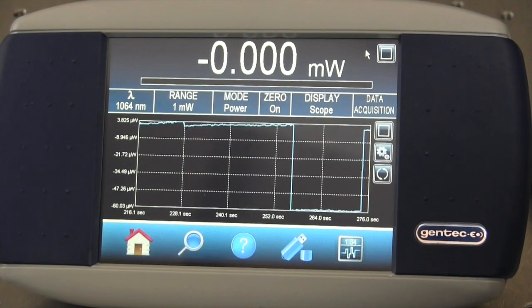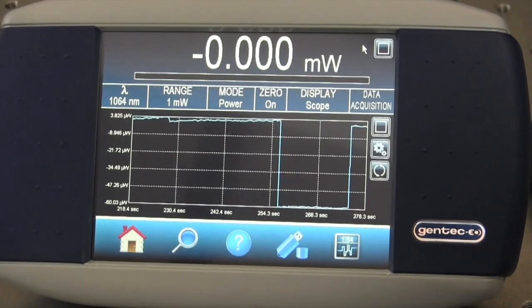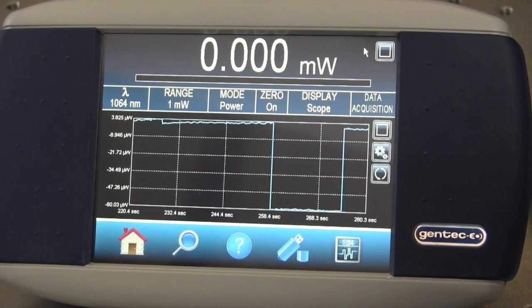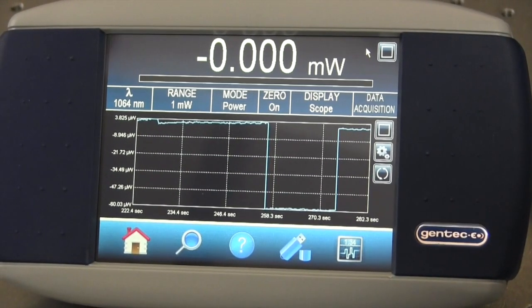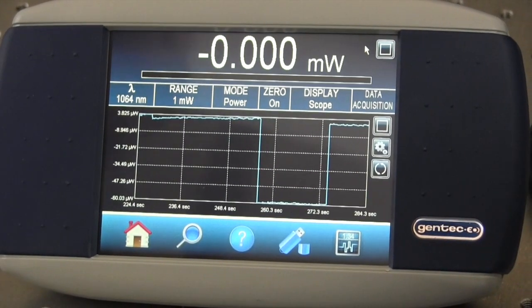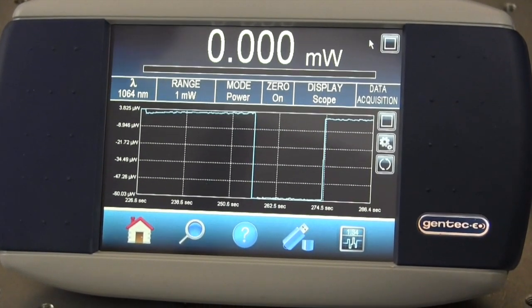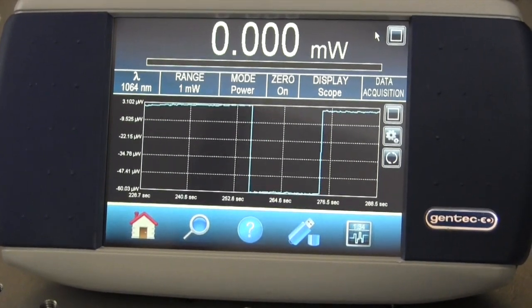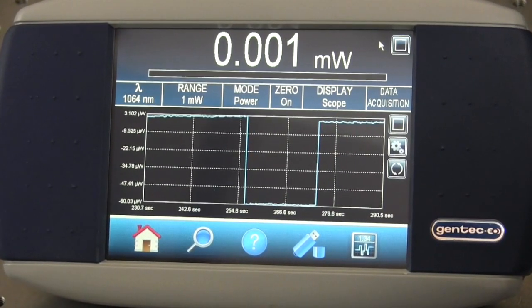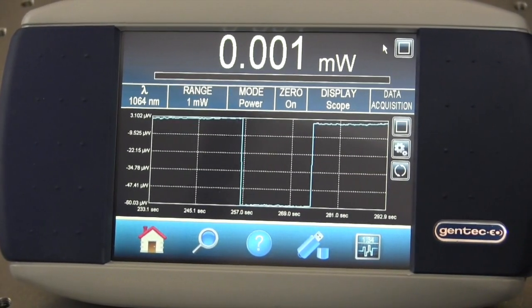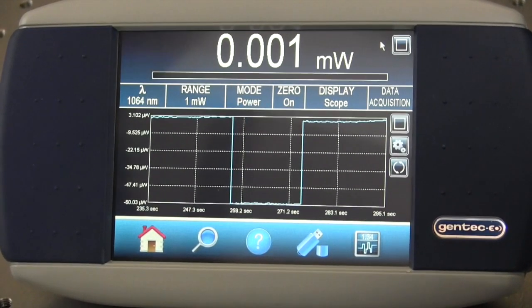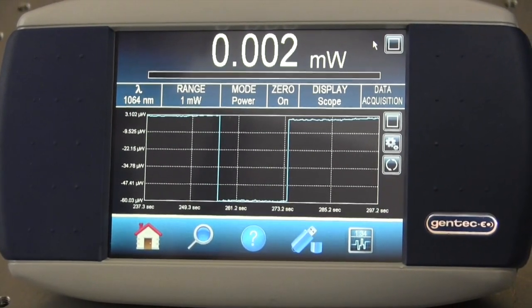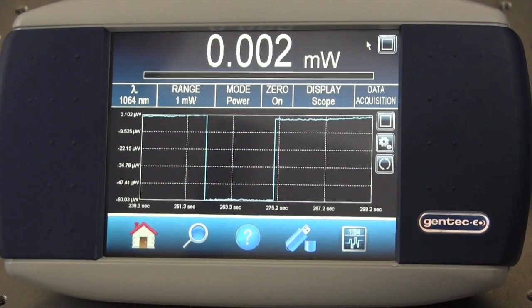making sure to stand clear of the probe. Once the display reads close to zero, you might have to press zero more than once. Let the system settle for about 1 minute. If the reading drifts up and down, this may mean that the probe has not yet reached thermal equilibrium. Give it another few minutes and repeat the procedure. Once you have a stable zero, you can measure the laser power.